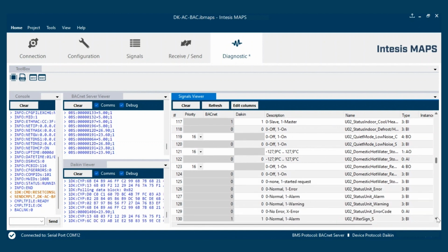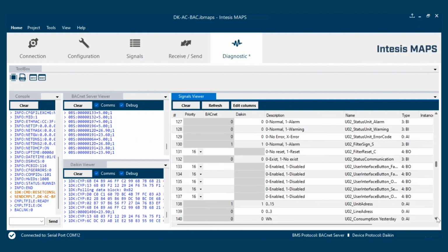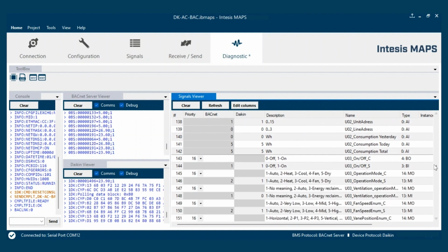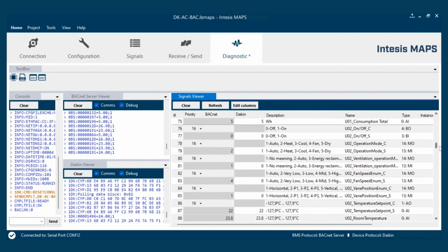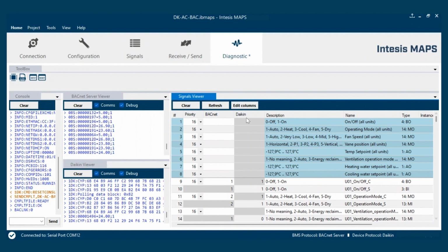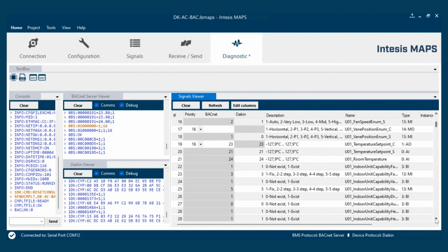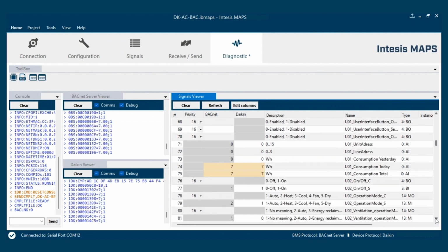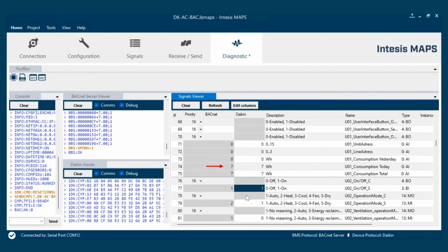These factors include the return air temperature, the position of the electronic expansion valve, and other reference values determined by the AC manufacturer. Based on these and other input parameters, the algorithm provides a reliable estimation of the energy consumed by each indoor unit. These consumption values are calculated and displayed in real time. We see, for example, that Unit 1 now shows 7 watt-hours of consumption.